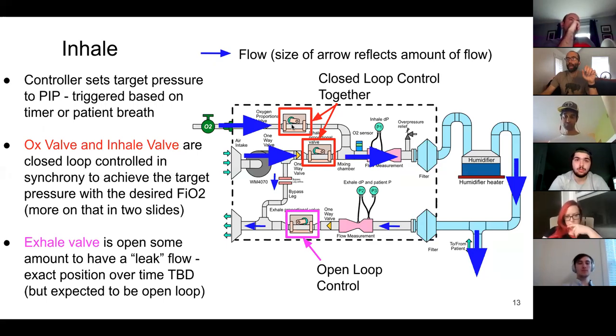So each of these valves, which we'll talk about the actual mechanical implementation later, is essentially controlling the flow of air or oxygen. Right now, the baseline assumption is that the fan is running open. The fan's just basically on or hitting a set point, and maybe that loop point changes, but there's no feedback in there. It's just on. And same with the wall oxygen pressure, it's just on and assumed to be fairly consistent, at least over seconds or tens of seconds.